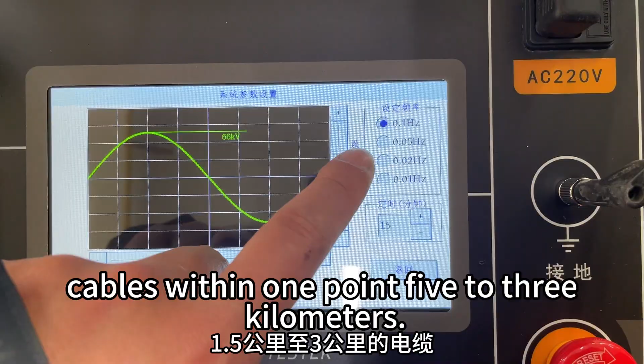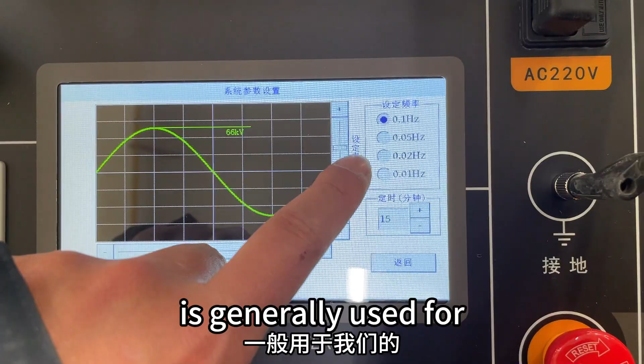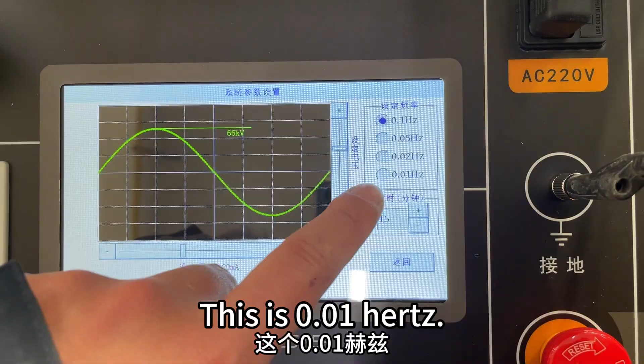0.05 Hz is generally suitable for cables within 1.5 to 3 kilometers. The 0.02 Hz is generally used for cables within 3 to 6 kilometers. The 0.01 Hz is generally suitable for cables over 6 kilometers.